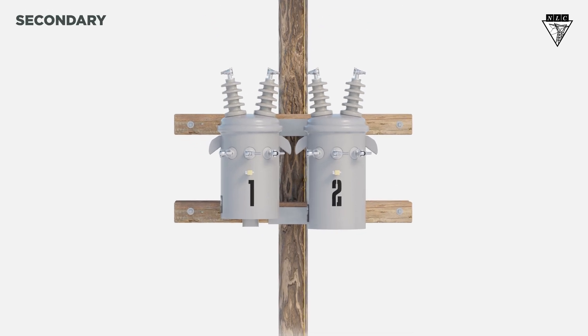Delta secondaries don't allow transformers to share the single-phase load equally. Therefore, one transformer must provide the lighting load, called the lighting transformer. This transformer will provide the majority of the single-phase load and must be larger in KVA than the other transformers.